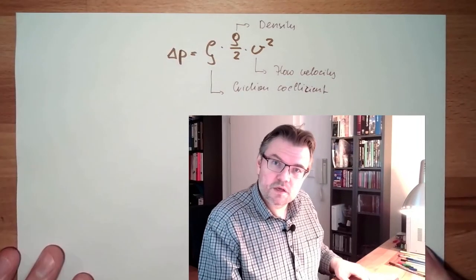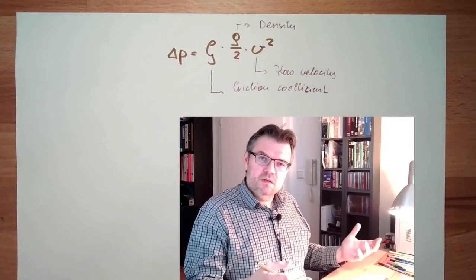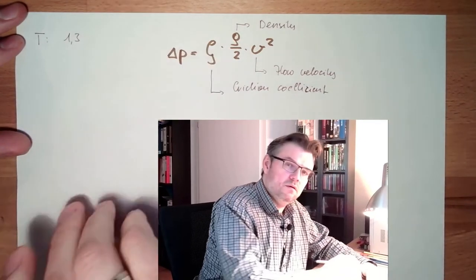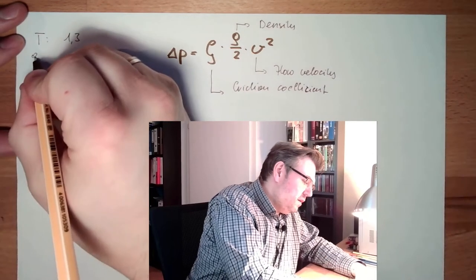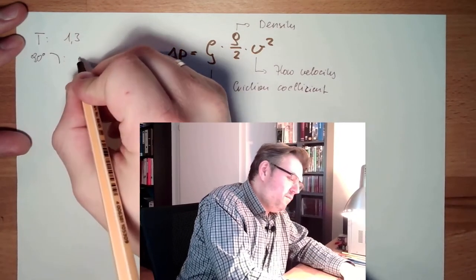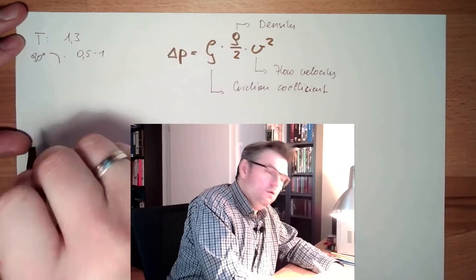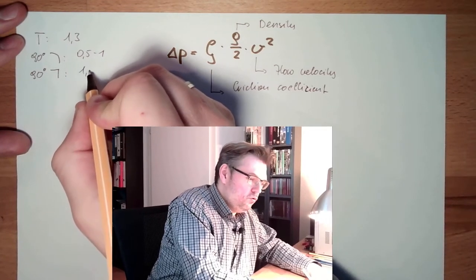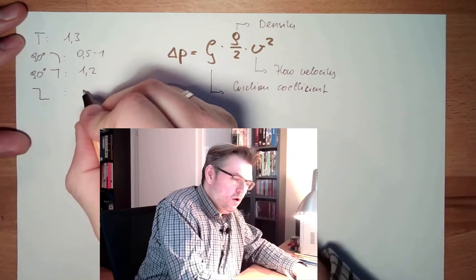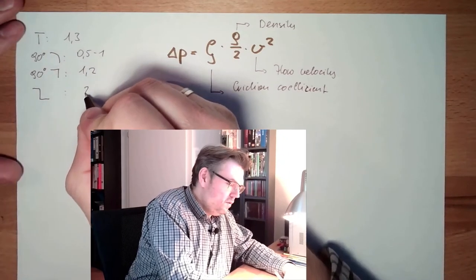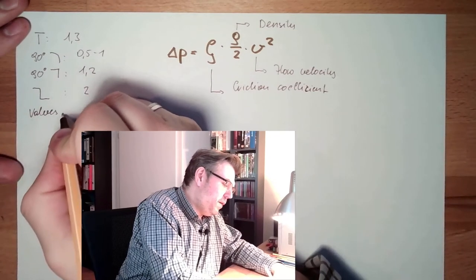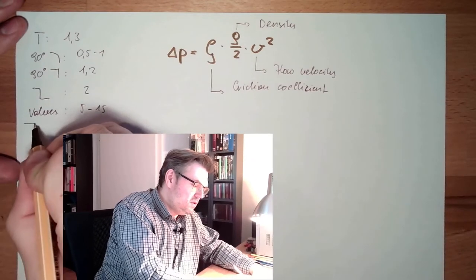This friction coefficient — the zeta value — depends on how the fitting is formed. If there is a T-piece, the friction coefficient is around 1.3. If there is a gentle 90-degree bend, it's around 0.5 to 1. If there is a 90-degree sharp edge, it's around 1.2. And for valves, depending on the internal design, we are somewhere between 5 to 15. These values are written in the database — these are my zeta values.